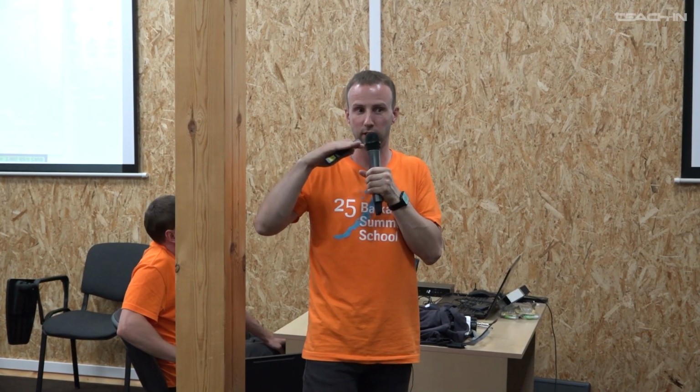Sasha, and what is the light source? The light source is the LED. As I said, it's here in the box. And this is a self-stabilized LED. What does it mean? It means that it has feedback which allows us to control the intensity of the light flash. It's a very stable light flash. The stability is less than 1%. So we have a very stable light flash, but a very low one, so we have single photons coming to the detector. Sometimes 0 photons are detected, sometimes 1, sometimes 2.